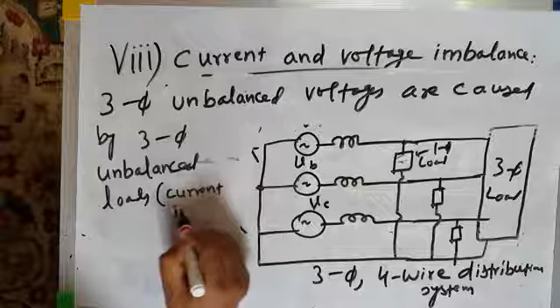When your load is not balanced, there is imbalance in the line currents. For example, this is line current IA, this is line current IB, and this is line current IC, and this is neutral current IN. Normally these line currents IA, IB, IC should be constant, so that the voltage applied here is VA minus this drop. The voltage at this point is VB minus the drop across this resistance, that is IB into X, and the voltage here is VC minus IC into X. And these three voltages should be constant. But if your three-phase load is unbalanced, then these voltages also become unbalanced.